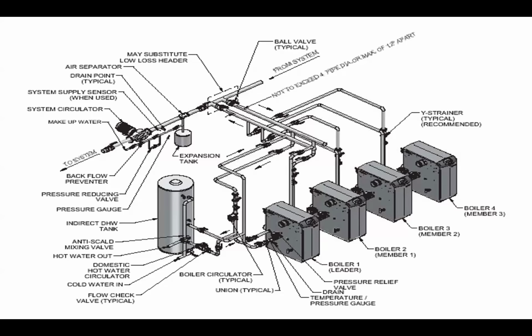And conversely, we have a distribution pump that's feeding whatever the case may be. It could be a campus, a hospital, a college campus, multiple buildings. It could be an apartment complex. It could be whatever it needs to be. We want to make sure that that distribution pump is hydraulically isolated from these individual boiler pumps. So that's a subject that we get into. That's a pretty important design subject.